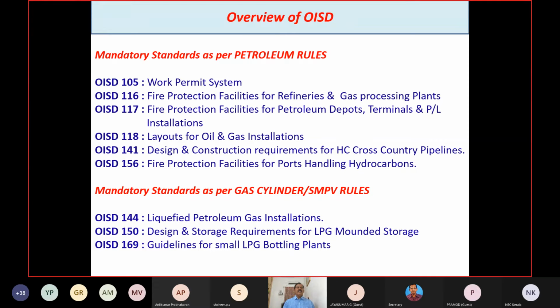And the mandatory standards as per the Gas Cylinders Rules and SMPV Rules, the Static and Mobile Pressure Vessel Rules. The OISD standard 144, Liquefied Petroleum Gas Installations, is specifically made for liquefied petroleum gas. And you may be aware that LPG is a highly dangerous explosive gas.